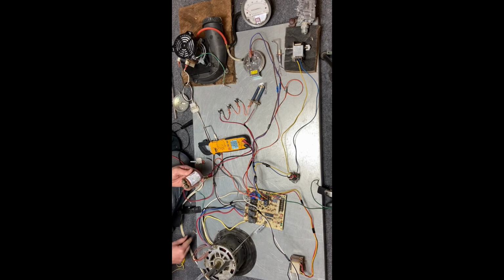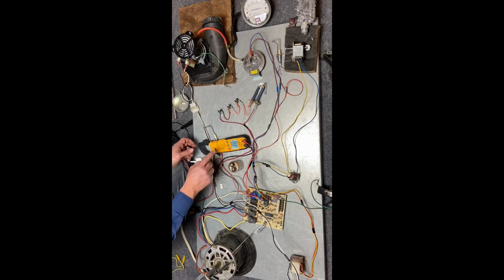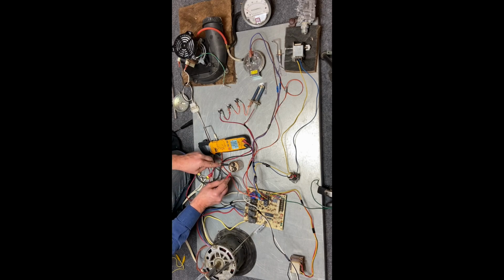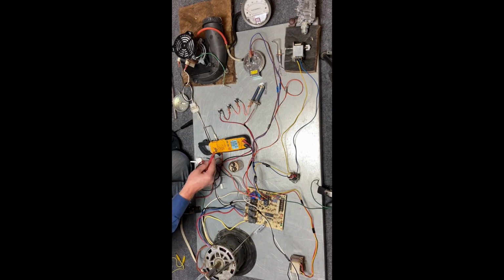So this is our capacitor. Now before I check this capacitor, I want to discharge it. I'm going to use a 20,000 ohm 5 watt resistor. I want to make sure I hold just the porcelain, and I'm going to touch these two terminals right here and discharge this capacitor. Now alternatively, if you don't have a 20,000 ohm 5-watt resistor, you can set your meter for voltage, turn it to DC, and you can let it discharge through your meter. In other words, it showed me a voltage just for a little bit. It allows it to discharge through the meter at a very even rate.